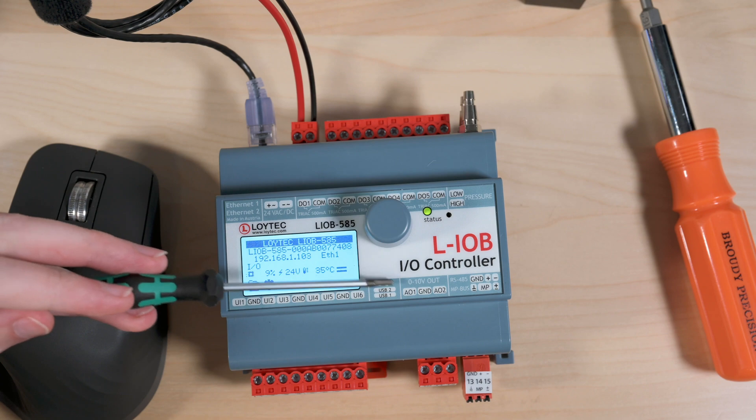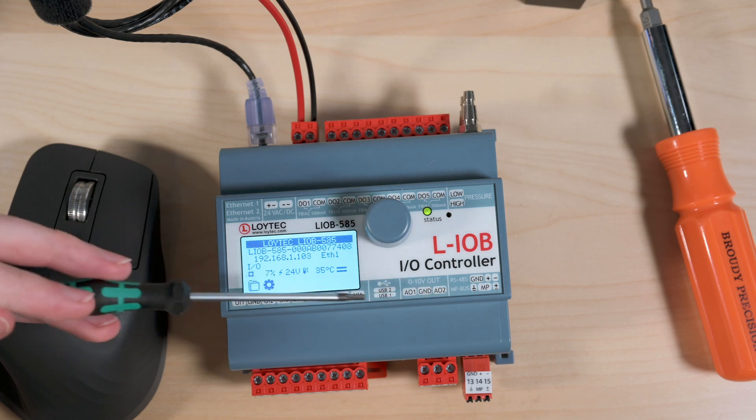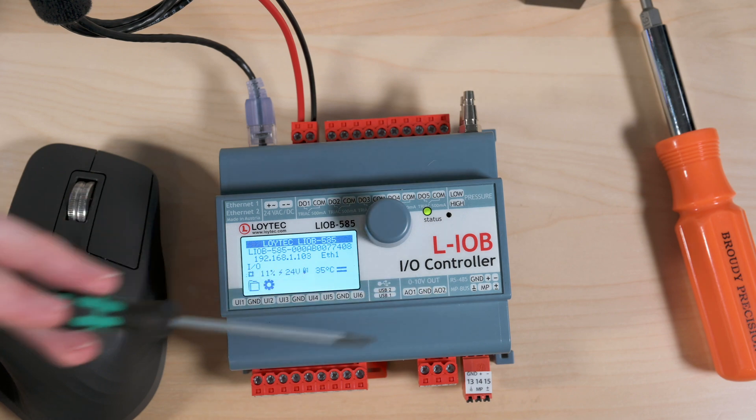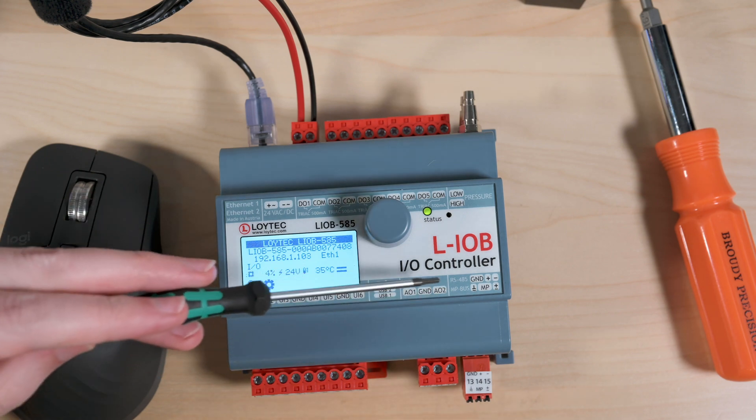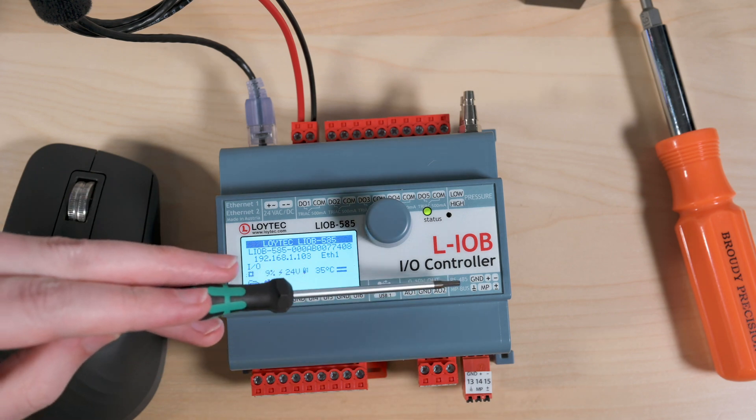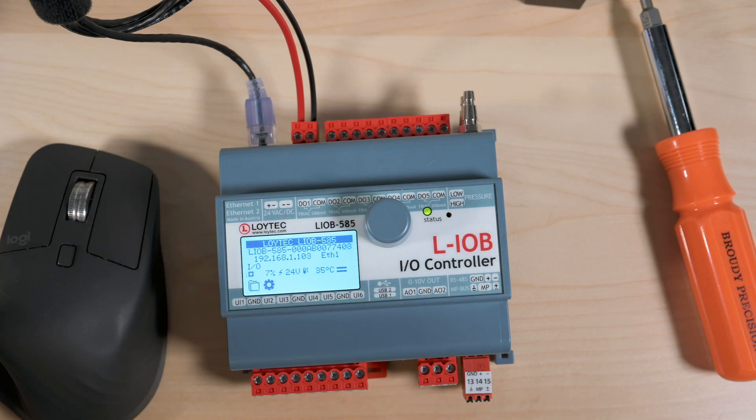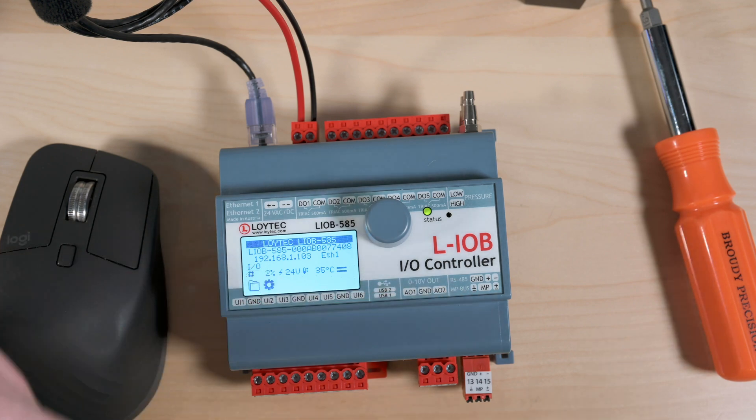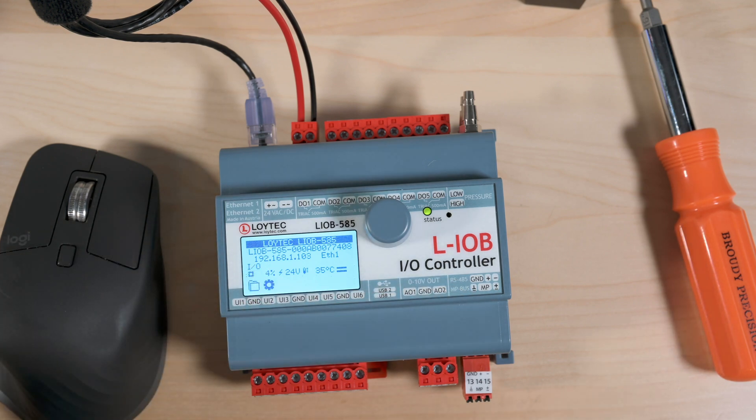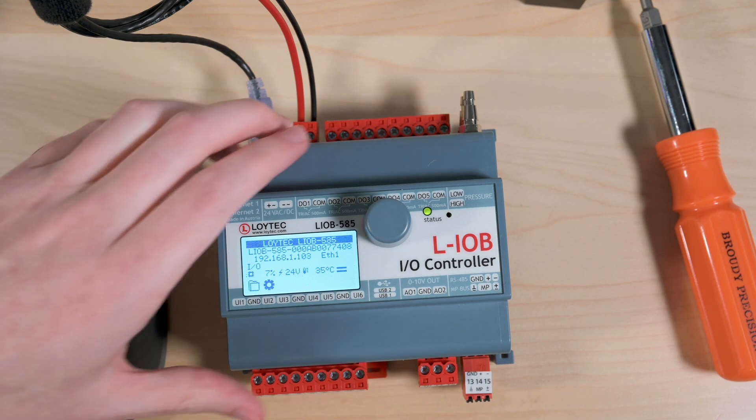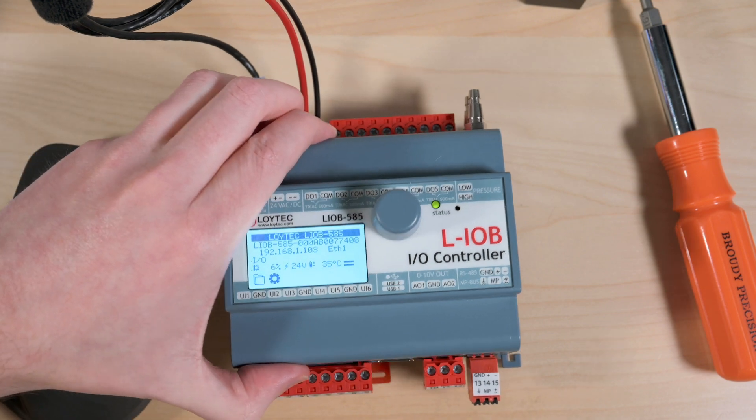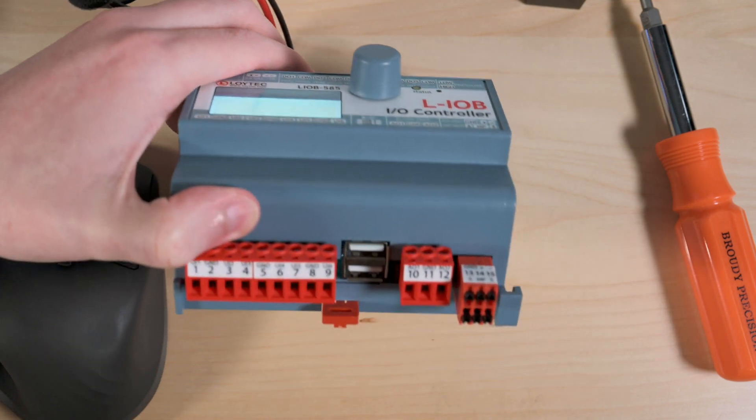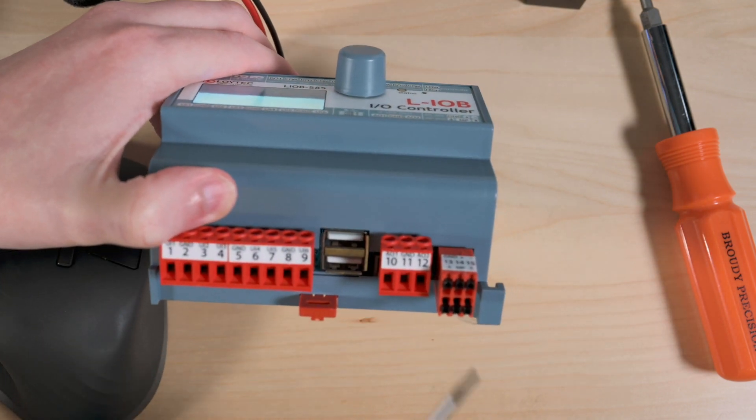Then we also have two analog outputs that do 0 to 10 volts. And then we have an RS-485 connection, as well as an MP bus connection. And that's helpful if you're using this in a terminal style where you're going to be connecting to actuators.